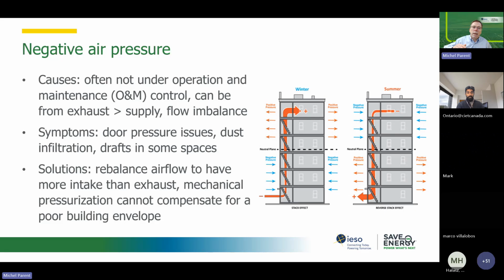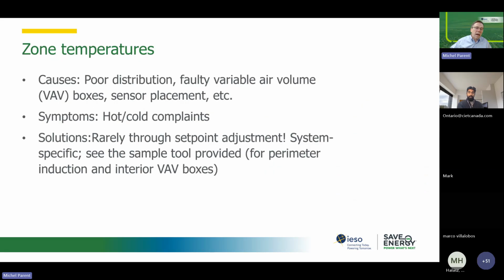Negative air pressure can be, in terms of pressure measurement, in the 200-300 Pascal level. Your mechanical system, for most buildings, cannot provide pressurization more than about 40 Pascal. So if you try to throw a lot of outside air to pressurize your building, you are basically wasting energy because you will not win that battle. The best way to resolve negative pressure issues, especially in a high-rise building, is to reduce the infiltration, because your mechanical system will not win that battle, especially if there's any kind of wind. Wind loading is 10 times, 100 times stronger than what your HVAC system can do.